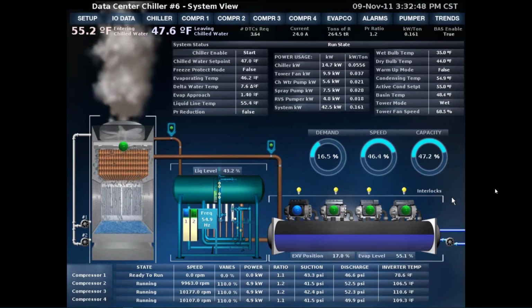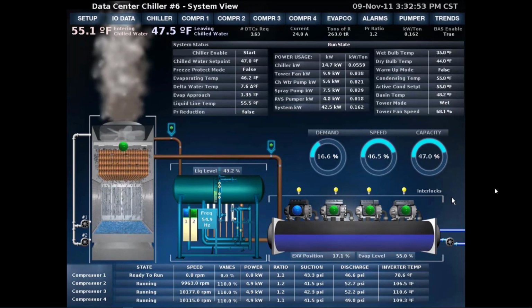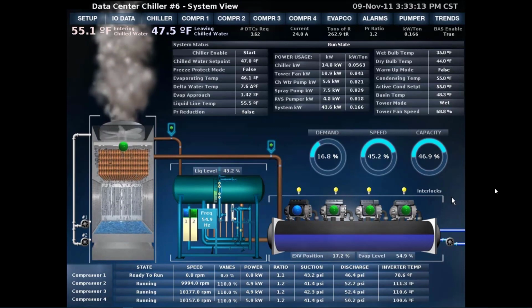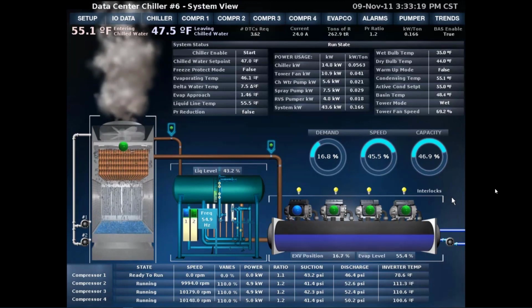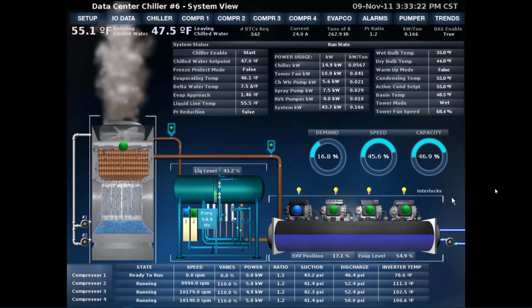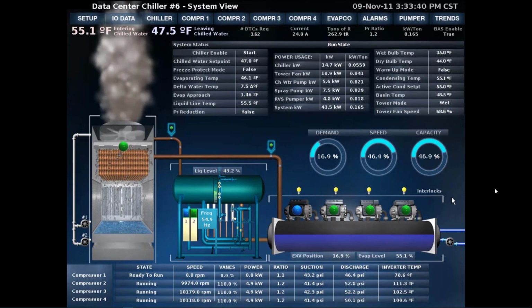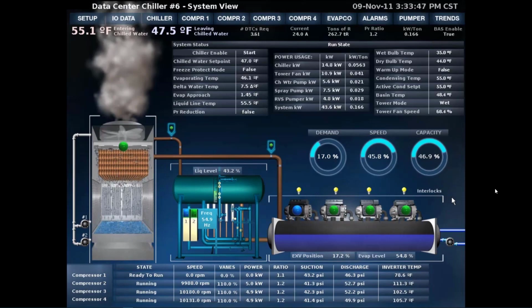It features evaporative condensing, a very large surge tank with refrigerant optimization, and 500-ton turbocore chillers. I want to point out the run state. The chiller kilowatts in this particular state, and this was real time at the time, was drawing 0.0563 kilowatts per ton. That's on the chiller. Tower fan 041. The point is that the entire system, by using this refrigerant optimization and using an evaporative condenser in a turbocore oil-free chiller, was able to get the total system kilowatts down to what we show here, 0.165 kilowatts per ton across the chillers, tower, chill water pump, spray pump, and the pump kilowatts. So this is just an amazing amount of technology that's taking place here, and we will have this available later this year.